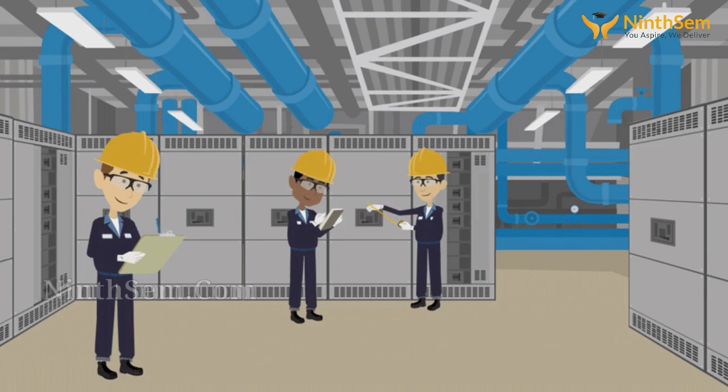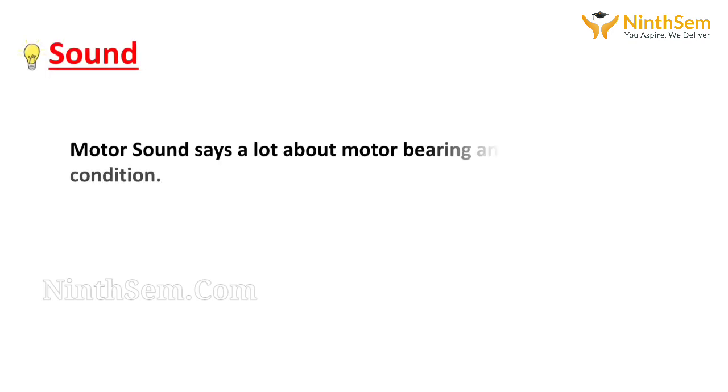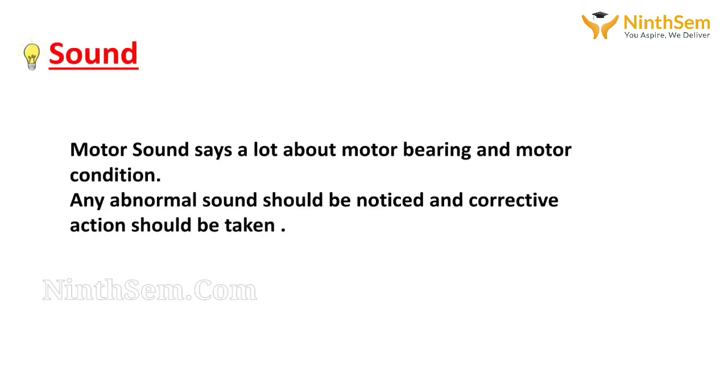Following parameters should be kept under observation. The first parameter is sound. Motor sound says a lot about motor bearing and motor condition. Any abnormal sound should be noticed and corrective action should be taken.